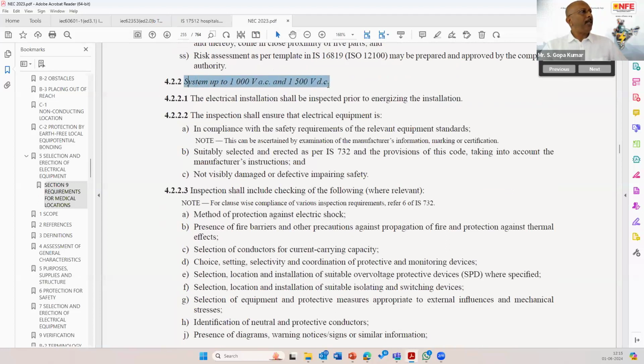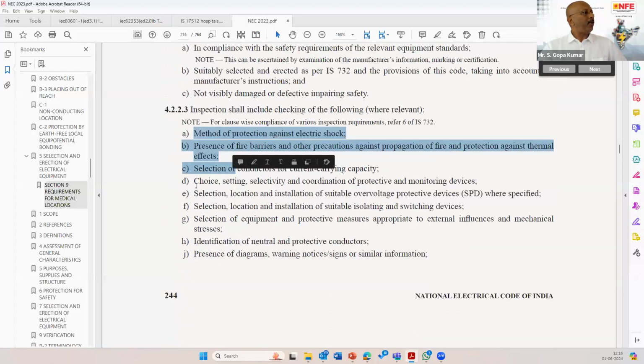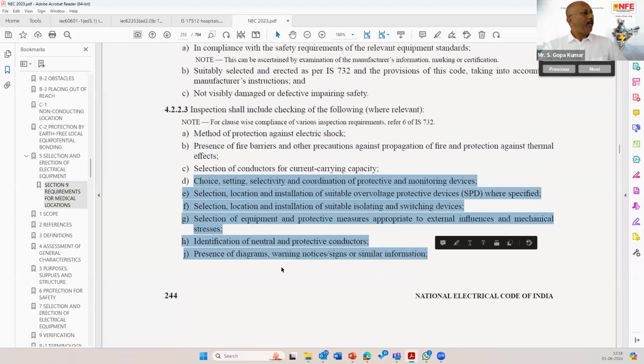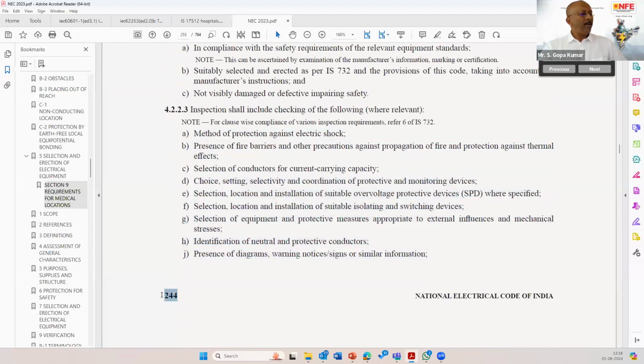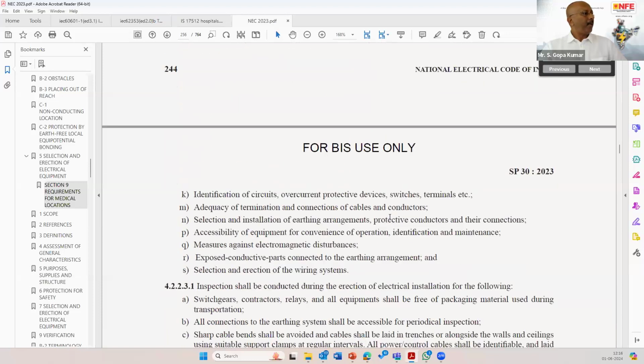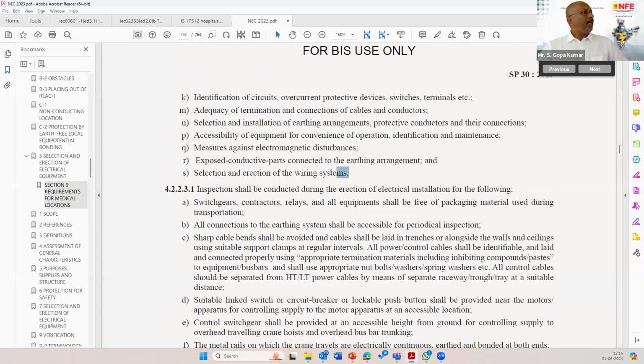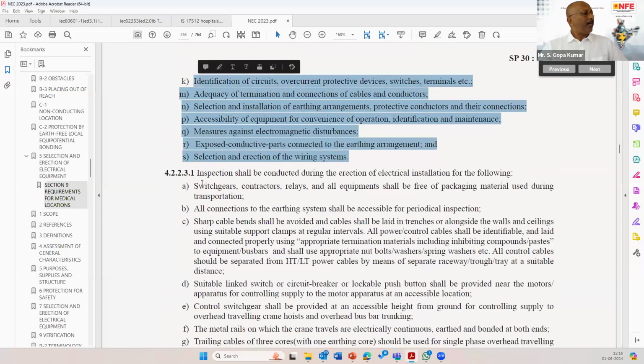Systems up to 1000 volt AC and 1500 volt DC: it consists of inspection and testing. Inspection shall include the checking of the following where relevant. It talks about methods of protection against electric shock. If you download the NEC, go to page number 244 and look at clause 4.2.2.3. This is about the inspection part. You can see items A to S are the inspection.